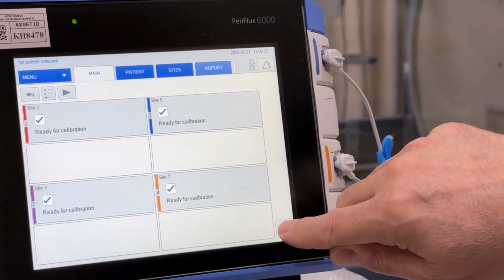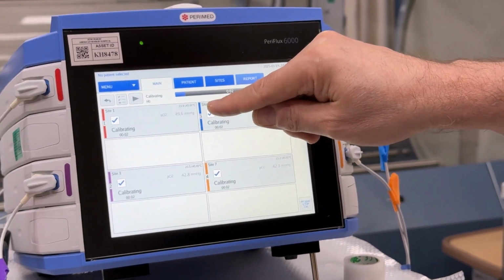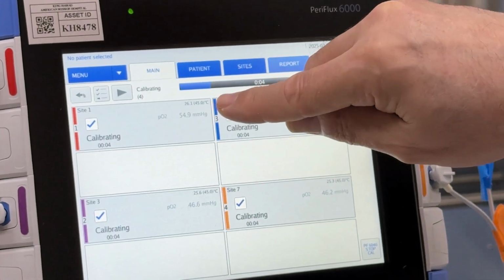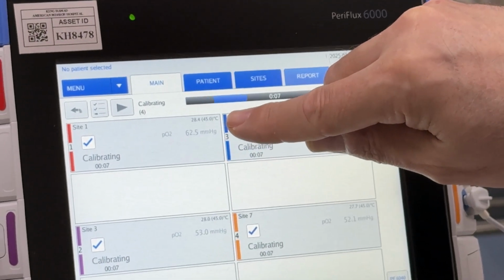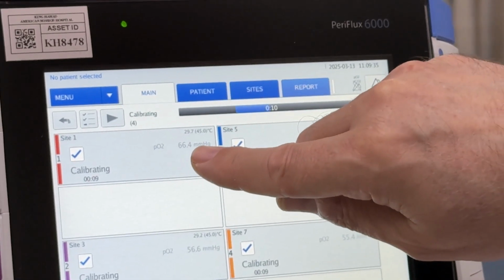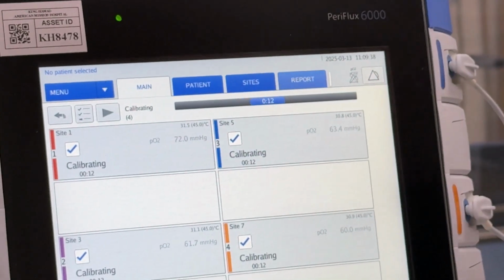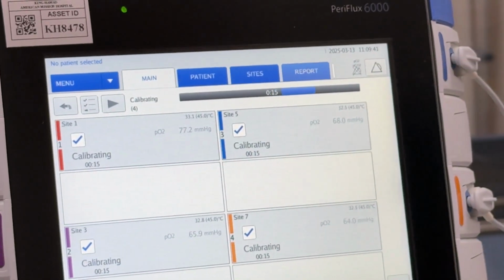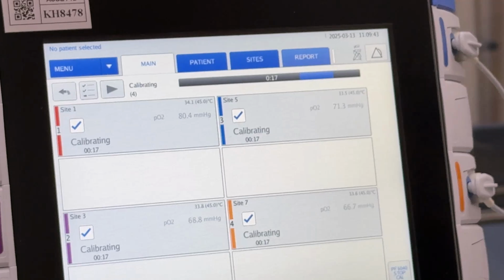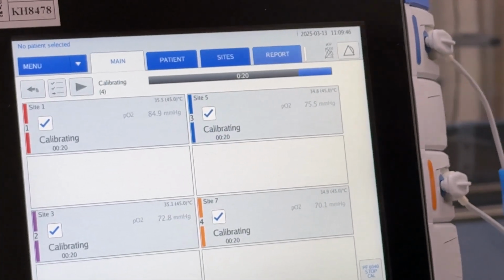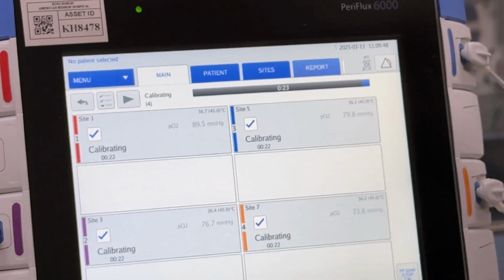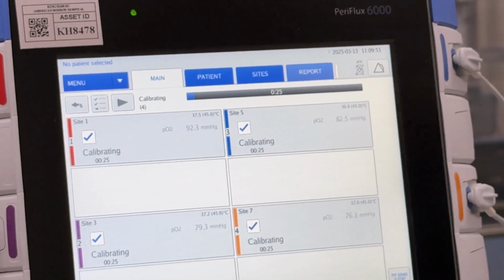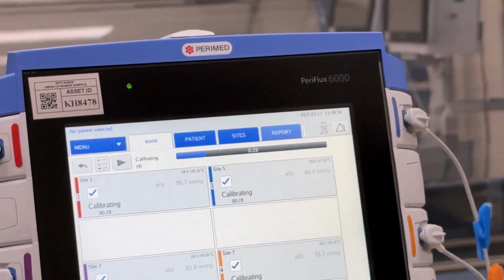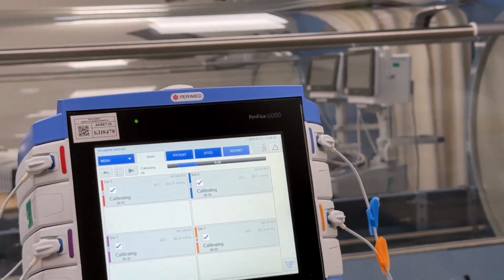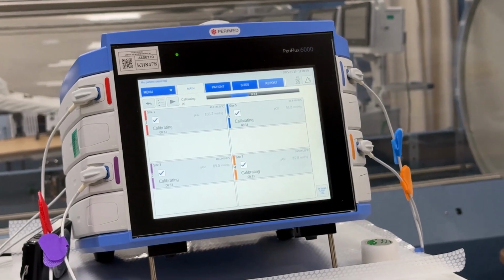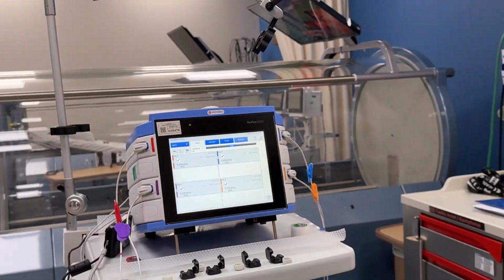So you now push this button, and you may notice the temperature of the electrode starts increasing, and it will heat up to 45 degrees. As it does, the measured oxygen, which is from the environment, will also change up to a value of 157. Once it's at that level, the electrode will be tested for any deviation, and if it deviates more than 2 millimeters mercury, then it will be rejected and the electrode needs to be recalibrated. This process usually lasts about 2 minutes.